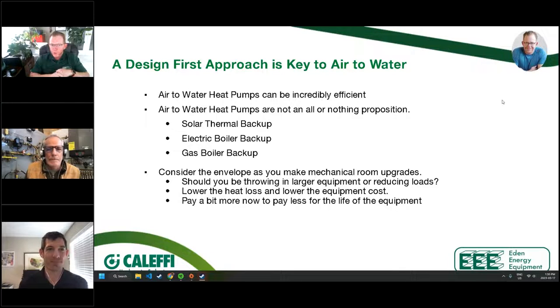The other thing is that when we talk about hydronic heat pumps, it's not an all or nothing proposition. There is a great case for hybrid applications, and Max talked about this. You can put an air to water heat pump in, and there's absolutely nothing wrong with having a solar thermal backup, an electric boiler backup, or even a gas boiler backup. In a retrofit application, which Max talked about, there are going to be scenarios where you simply cannot meet the load of this old building doing an air to water. But the reality is, if you do an air to water with a small electric boiler or a small propane boiler, or whatever fuel you choose as backup, we can meet those loads.